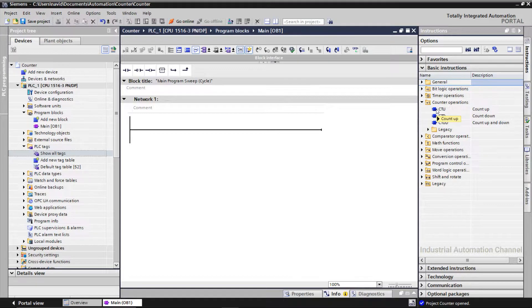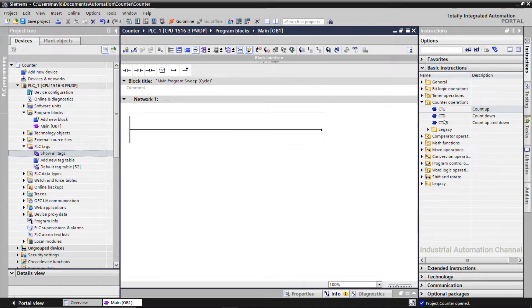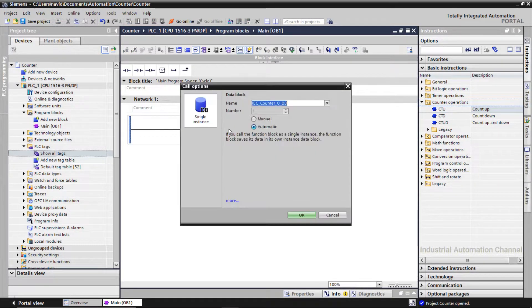The first counter is up counter CTU. Let's say for instance I want to count up the number of times an input goes from 0 to 1, and when it's repeated 5 times I want to turn on an output. For this purpose we can use the up counter. Like timers, TIA Portal needs to define an instance data block to save the data of the counter, such as the status of input and output.